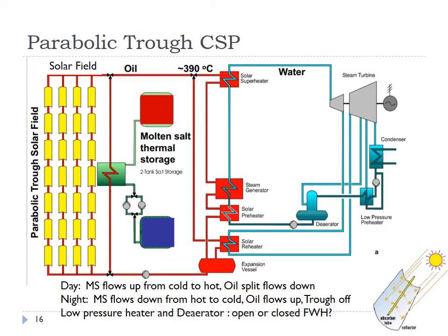During the day, some oil is split off and goes through a counterflow heat exchanger. Here, molten salt flows counterflow from the cold tank to the warm tank as the hot oil goes through and loses some of its heat, then mixes with the cold oil that went through the Rankine cycle and gets reheated in the trough.